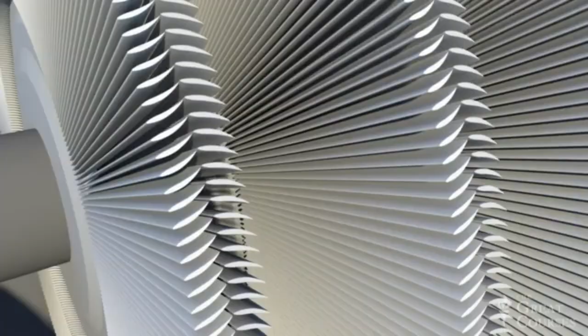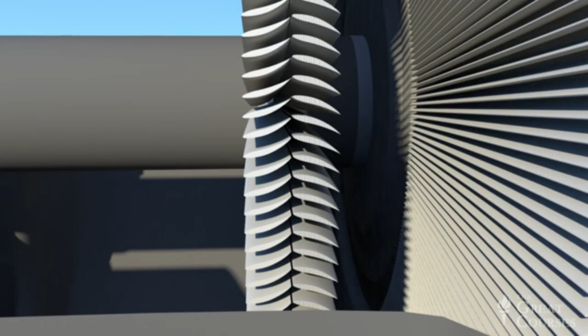Each pairing of one stator and one rotor is called a stage of the turbine. And here's how it works. High pressure steam enters at the narrow end of the turbine and it moves toward the wider end, passing through successively larger stages and expanding as it goes. The blades of each stator are configured such that the flow of steam through them is constricted. And just like wind blowing over the roof of a house, when the steam flows through this constricted space between the blades, it speeds up.